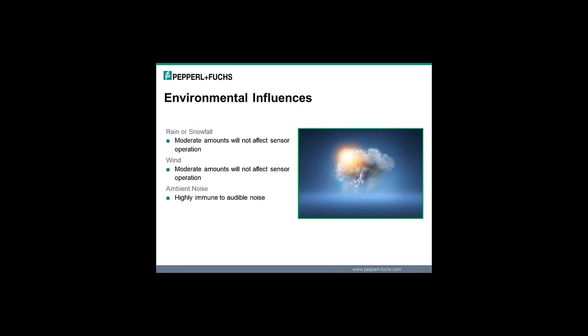And also ambient noise. Now, back in the old days, in the early days of ultrasonic sensors, some of our competitors had little shiny metal transducers that you could jingle your car keys around or blow an air hose by, and they would immediately affect the output of a sensor. So some people, if you've been around a long time, maybe gave up on ultrasonics because of those problems. That's not really the case with our Pepperl+Fuchs ultrasonics. Those have an extremely high immunity to any kind of audible noise. They're on a different frequency, and it's coded. The sound is coded, so it's very difficult to have any effect, regardless of the decibel level, for ambient noise to affect our ultrasonics.